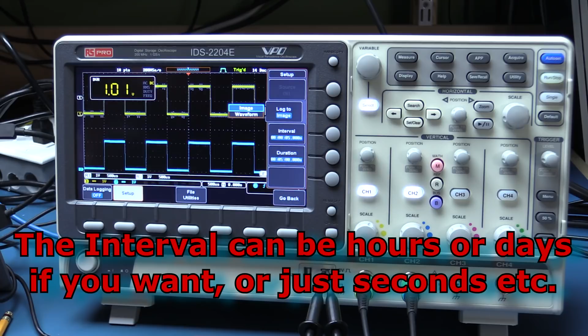So these are, remember, all of these are built in to this as standard. So DVM still turned on, so you can see you can run multiple of these apps. To turn data logging off, you can set it up to log images or waveforms. So waveform memory or image, just take a snapshot of the screen and the interval of what you want to log. So this is one of the features that they mentioned in the brochure that basically says you can capture images over a long period, so you could leave this running for a couple of days, and every 5 seconds you can have it capture an image and save it to a USB stick or remote drive if you set that up or something like that. And this waveform, I think, is sending the waveform data.